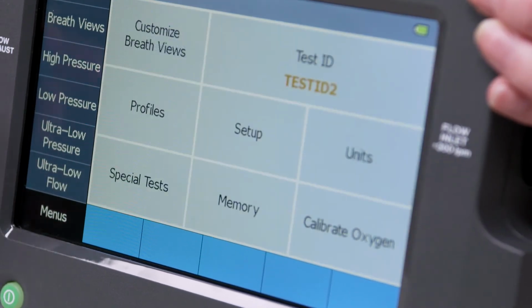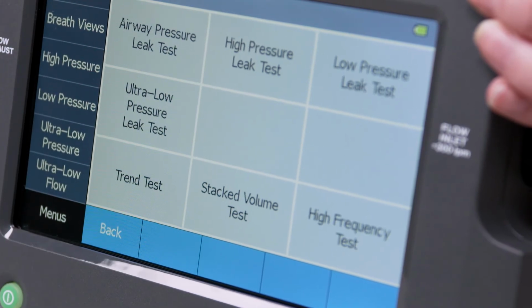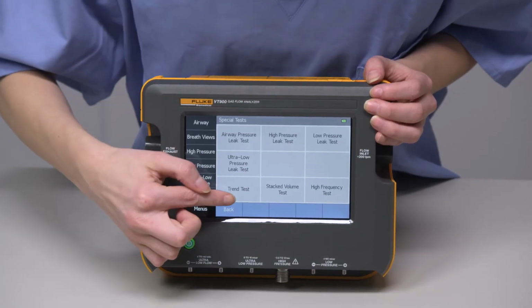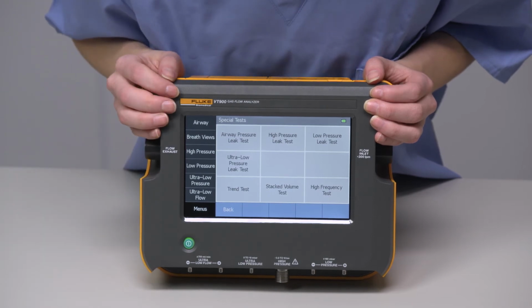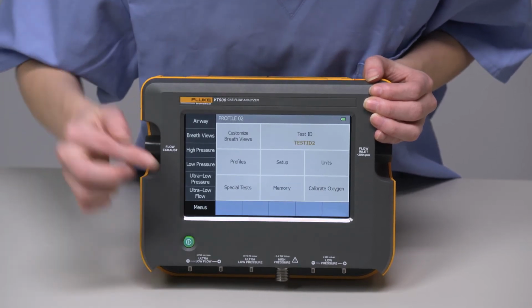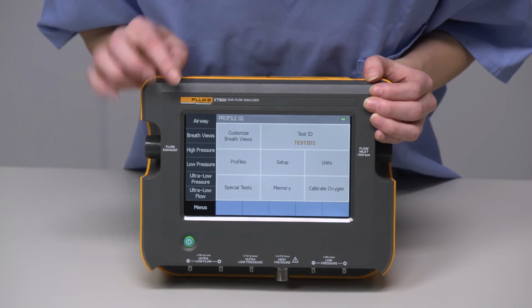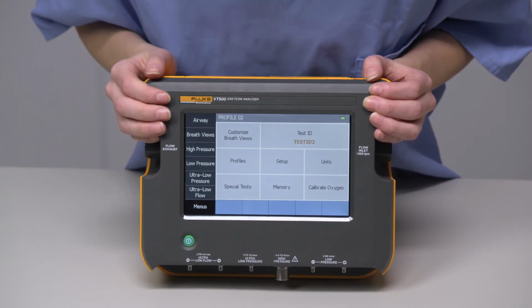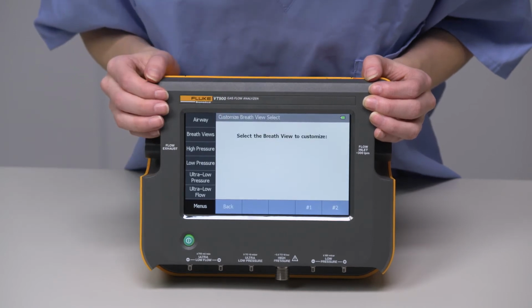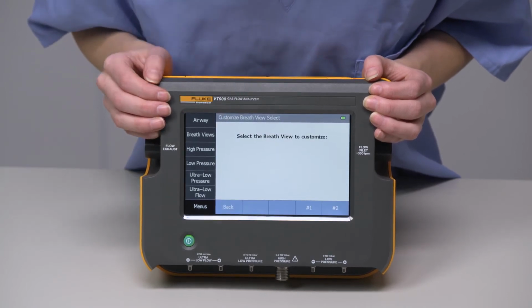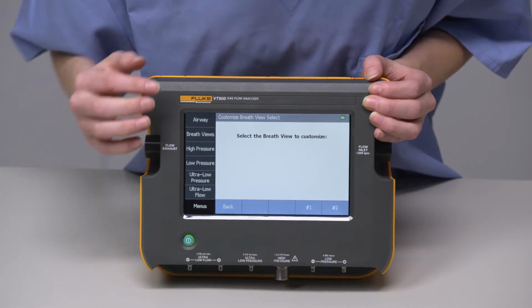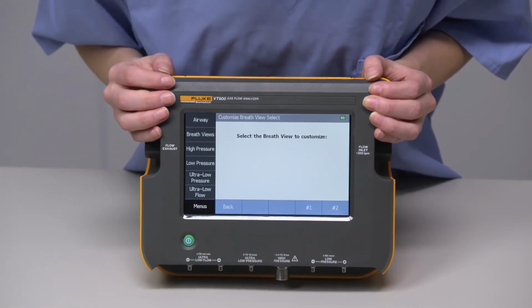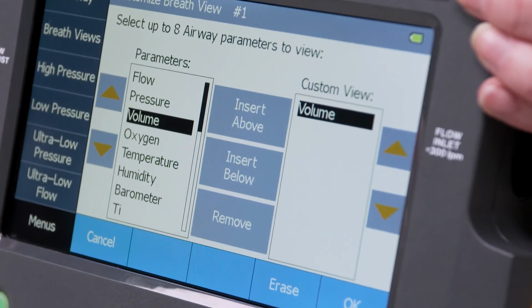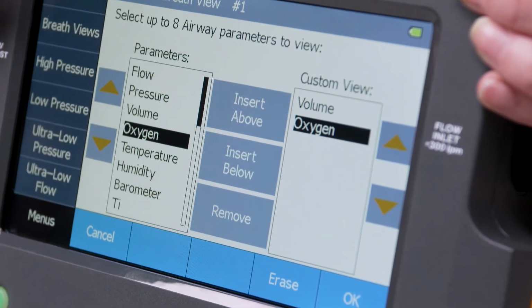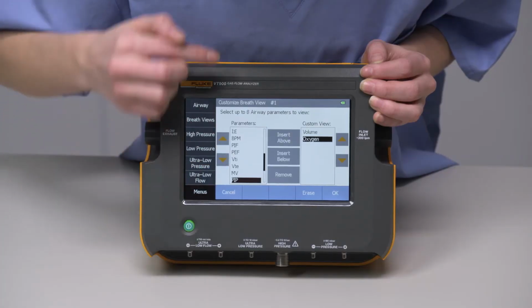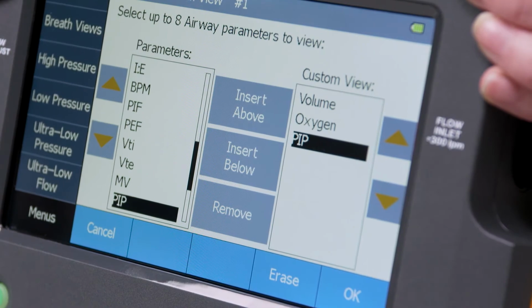The Special Tests menu is a list of various tests, such as leak tests, trending tests, stacked volume, and high-frequency tests. The last things we need to cover in the main menu are Customize Breath Views and Test ID. Customizing a breath view means creating 1 or 2 custom screens that show only what you want on them. Let's say we want one custom screen, and on it we want to show volume, oxygen, and PIP. We select those and then press OK to save.